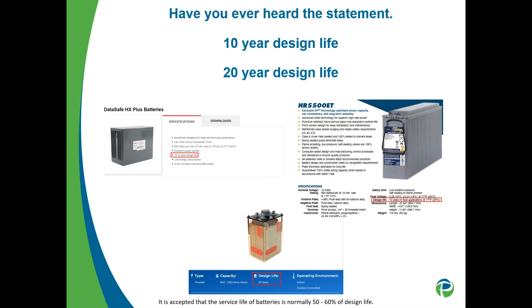So why do battery manufacturers push that number out so high? A lot of times these batteries are tested in a perfect environment - single source charged, so they have the exact float voltage the whole time of the design life period. Sometimes it's calculated based on the materials used in the chemistries and the electrochemical process. It's in a very controlled environment too - a pristine 25 degrees Celsius, 77 degrees Fahrenheit - and it's never cycled. That's why the design life is so much longer.